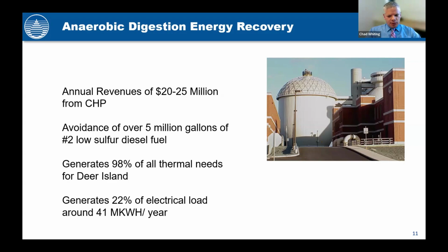The digester gas is used as a fuel source in a 235 million BTU boiler. We have 2 of those, run one at a time to generate steam, to provide that steam to the heating loop that runs completely around Deer Island to heat the digesters in all 52 buildings on the island. The excess steam is then sent to an 18 megawatt steam turbine generator to generate electricity. This process generates about 22% of the electrical load of Deer Island, approximately 41 million kilowatt hours per year.